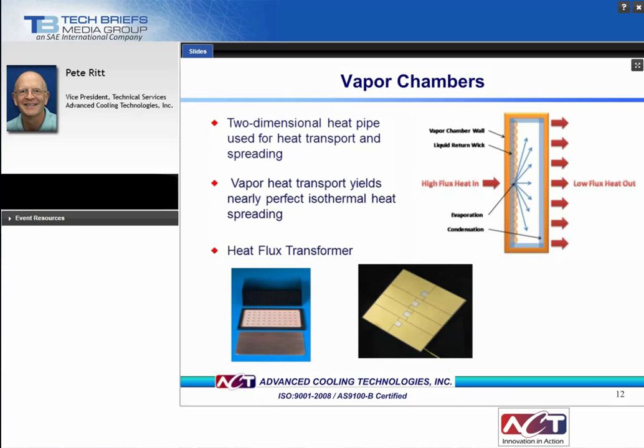Vapor chambers are often used in conjunction with heat sinks, taking advantage of their nearly isothermal output and making the heat sink more efficient. Typical components of a vapor chamber heat sink assembly are seen in the lower left. They consist of the vapor chamber wick structure in the middle, a copper envelope seen below, and a heat sink seen at the top. Also pictured is a multiple evaporator, low CTE (coefficient of thermal expansion), high heat flux vapor chamber prepped for direct die attachment of four chips. As can be seen, vapor chambers can accommodate multiple evaporators. This vapor chamber can accommodate heat fluxes of 700 watts per centimeter squared.